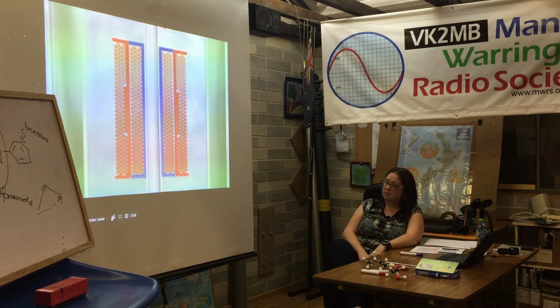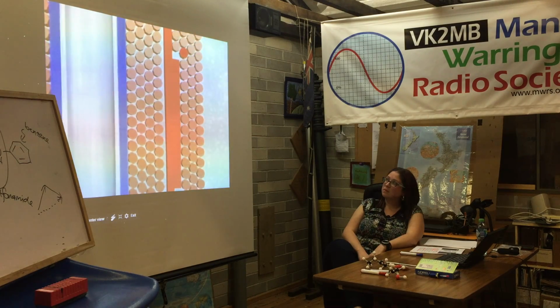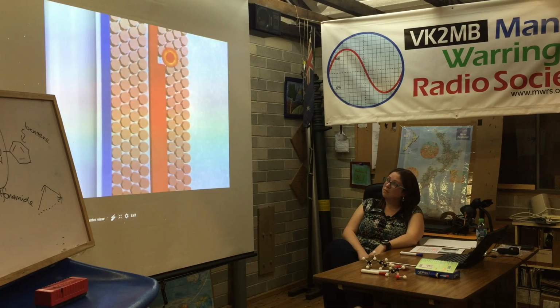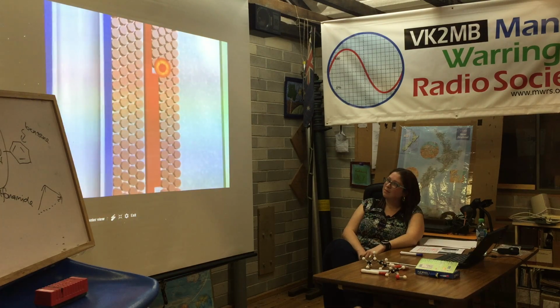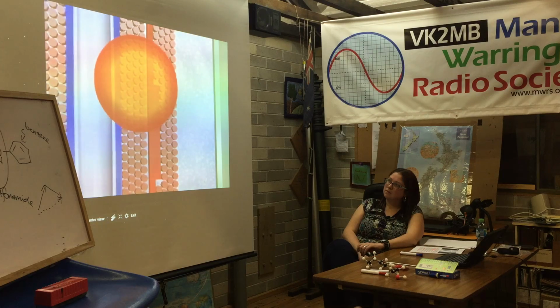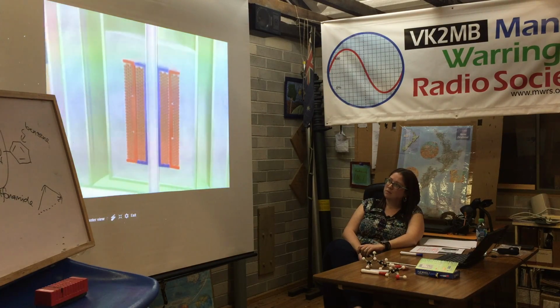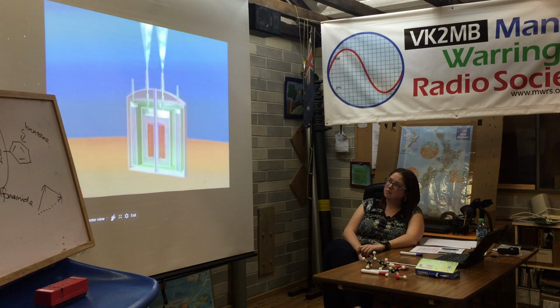These forces may cause a wire section to move within the coil by fractions of a millimeter. Such a small movement in a magnetic field can produce an appreciable amount of heat, so that the temperature of the wire section rises above the critical temperature of the superconductor. Hence, the wire section again shows an electrical resistance. Since the current still flows in the magnet, more and more heat is produced. As a result, the neighboring wire sections and, finally, the entire coil becomes normal conducting. The magnet coil is said to be quenched. The whole amount of liquid helium is vaporized by the heat generated in the magnet and escapes from the cryostat.